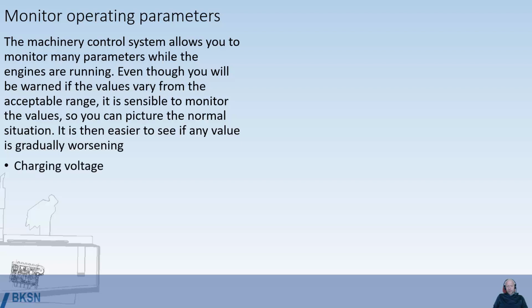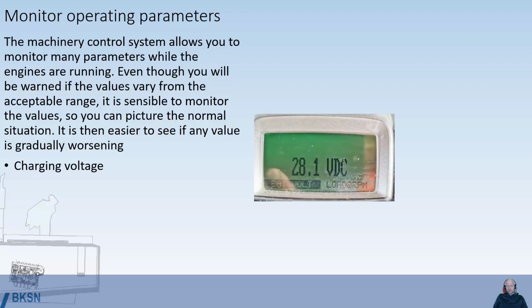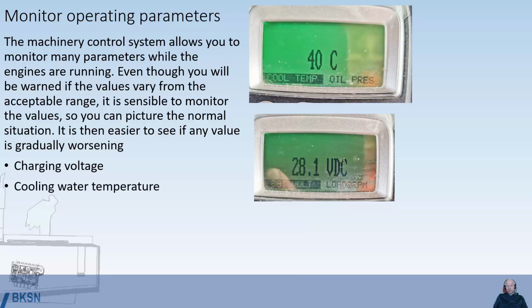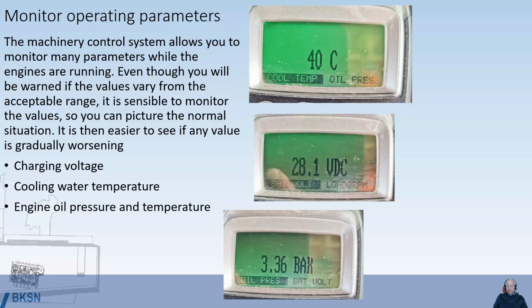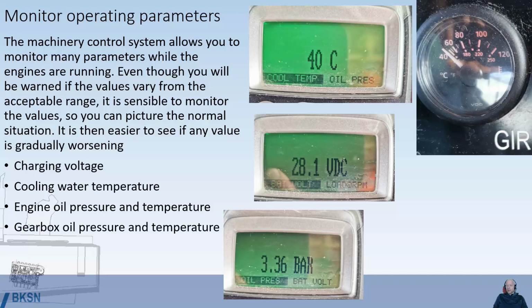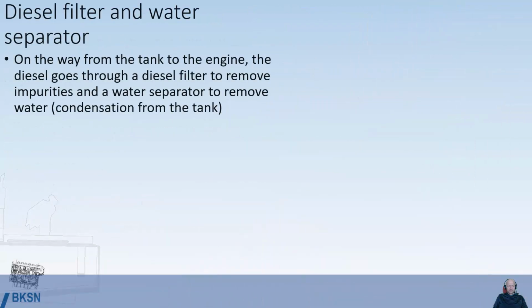Charging voltage, you can see a 24 volt system here, so it's charging with 28 volts, so that sounds good. Cooling water temperature, 40 degrees centigrade, and this was where the engine had not properly heated up. Engine oil pressure and temperature. You should have an idea what are normal values here. As well as gearbox oil pressure and temperature. You should have gauges for all these.